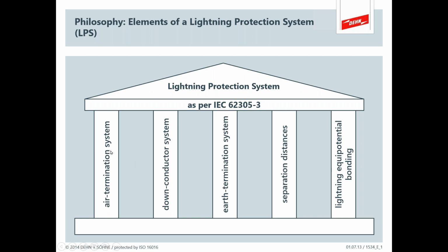The air termination system is what you want at the top of your building. The down conductor system brings that lightning current to the earth termination system, all while paying attention to separation distances between structures you don't want talking to the lightning, and bonding for structures you cannot prevent from talking to the lightning. We'll look at what that actually means: you cannot prevent a strike on something like the metal foundation of the building, so you bond it. But if you don't want it to talk to the antenna, you separate. That's really what that means.